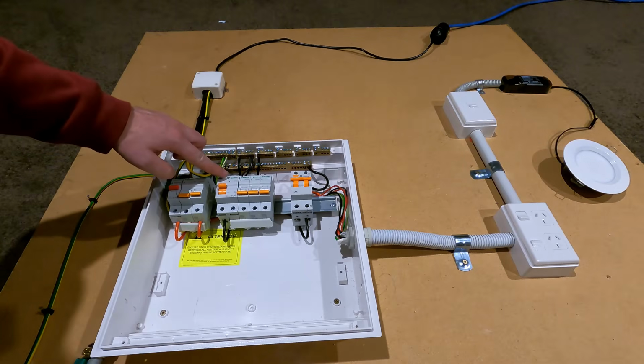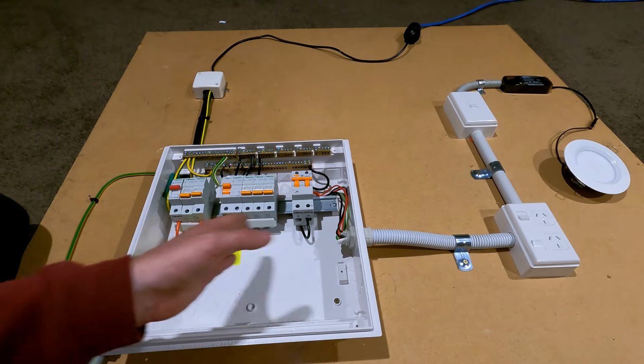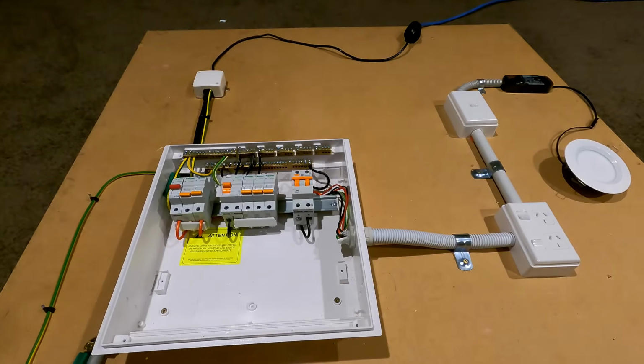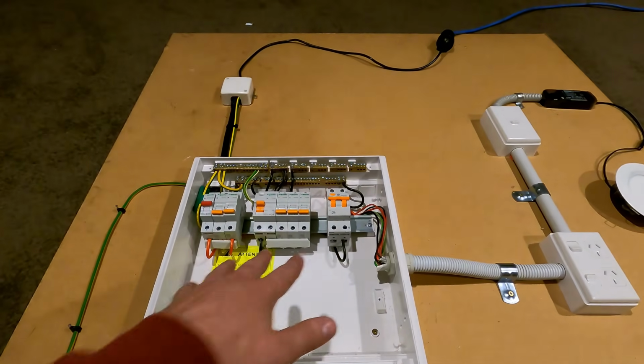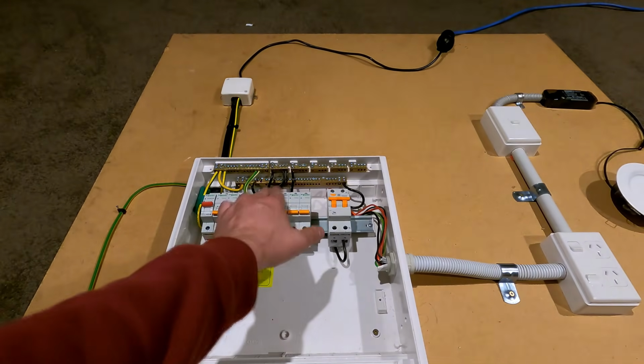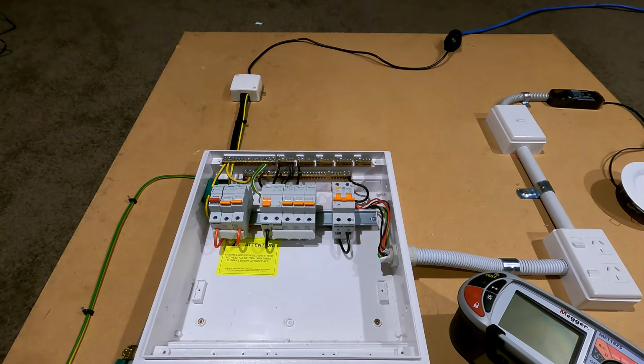And we're going to do our manual test. So we've verified the RCDs are functional. I'm probably getting a wee bit carried away with these RCDs at the moment, but all of them are set up properly.